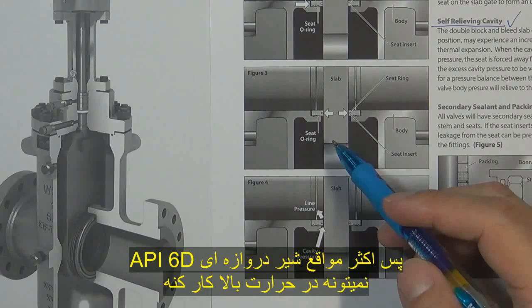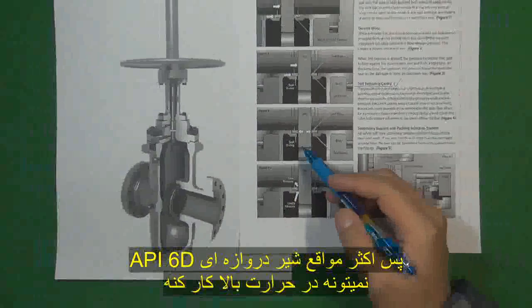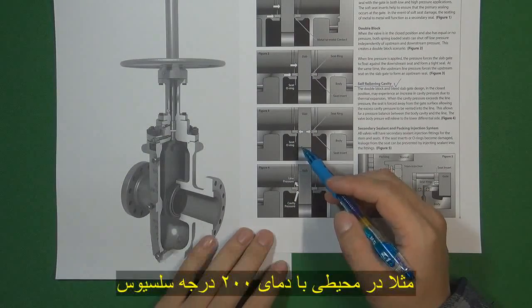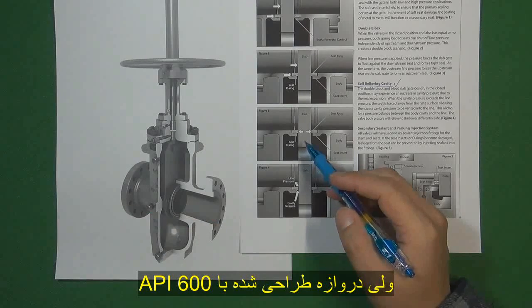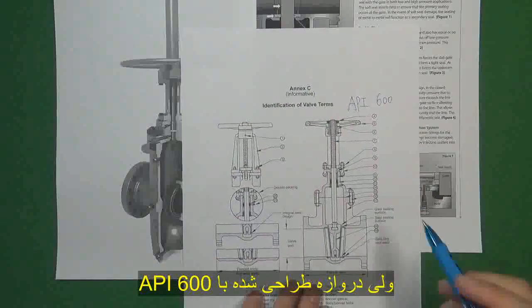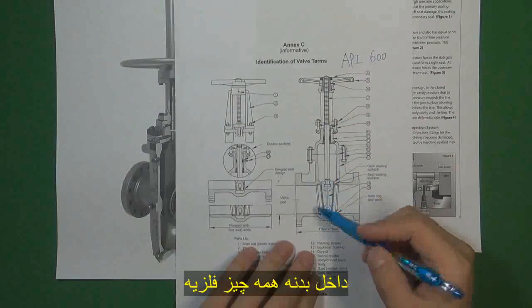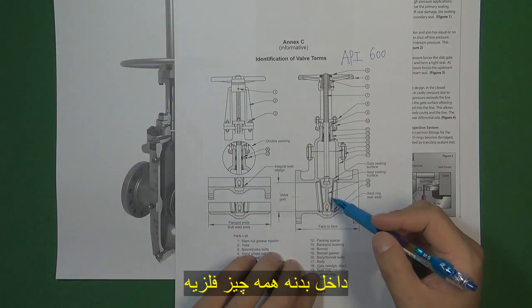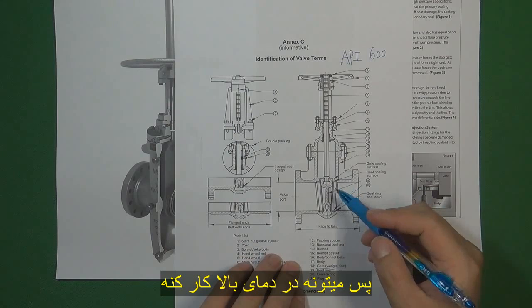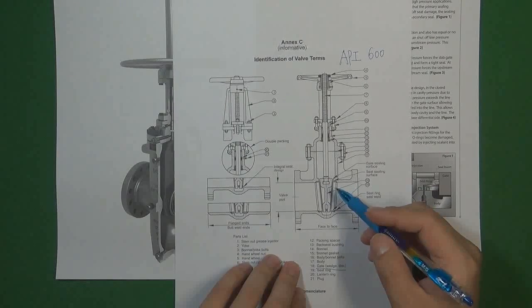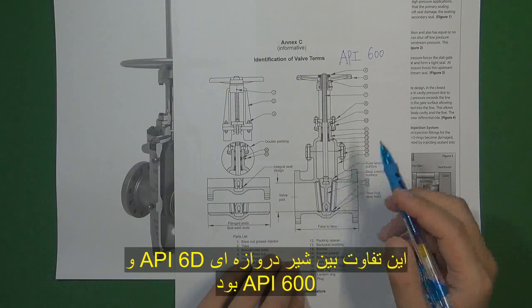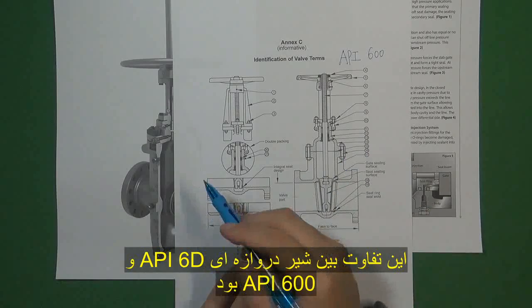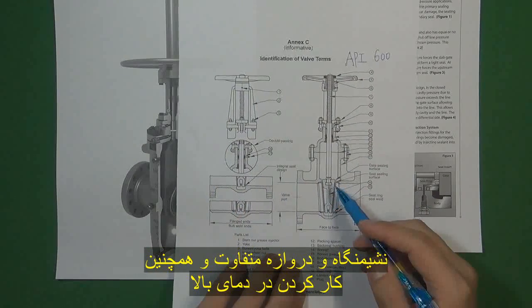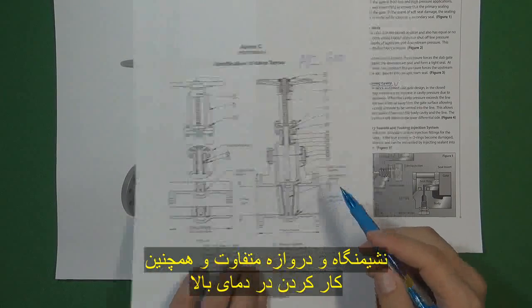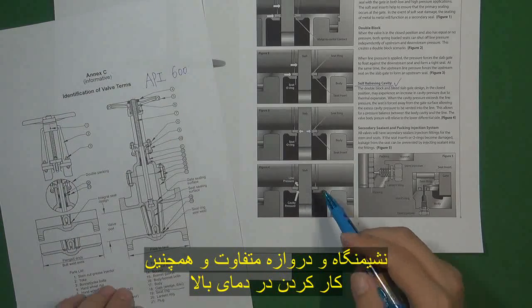So most of the time the API 6D gate valve cannot work in a high temperature environment, like 200 degrees Celsius. But in the gate valve designed by API 600, inside the valve body, everything is metal. So this kind of gate valve can work in a very high temperature environment. So that is the difference between API 6D and API 600 gate valves. Different valve seat, different valve gate, and different valve working temperature environment.